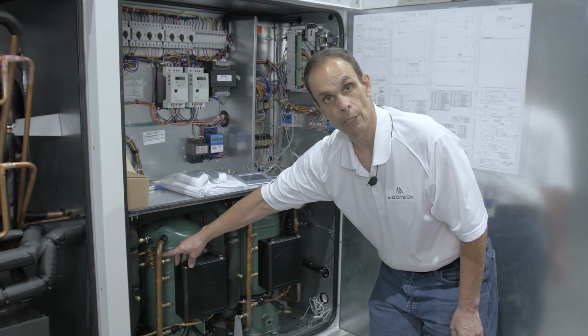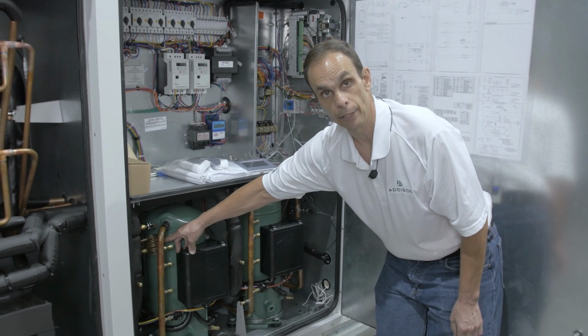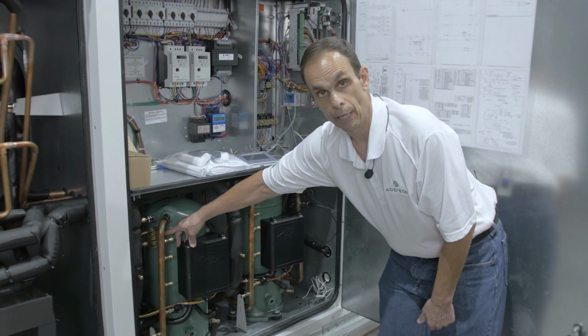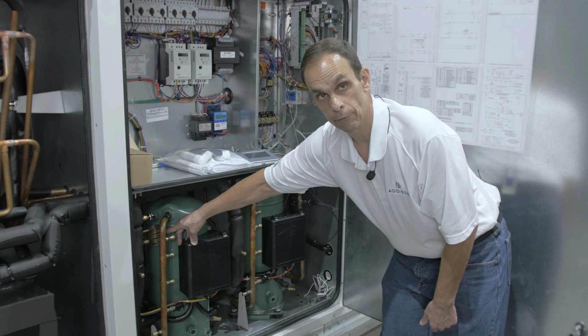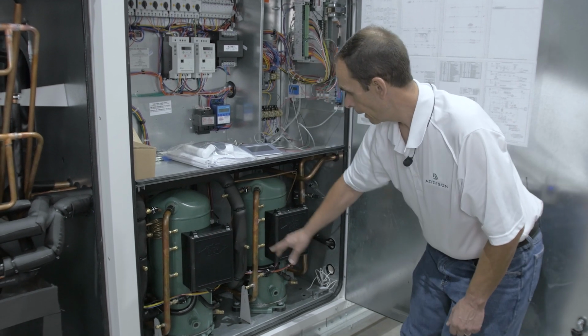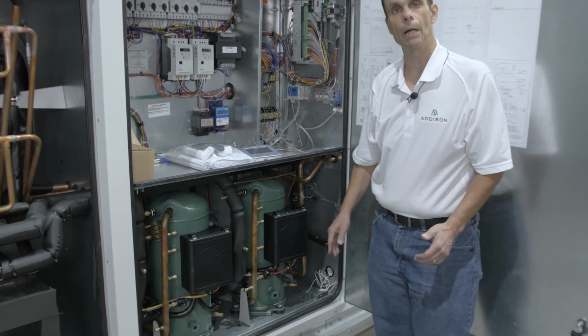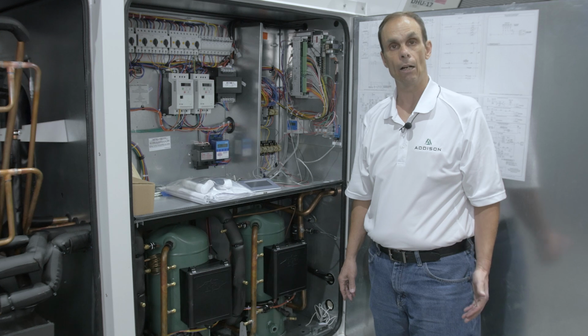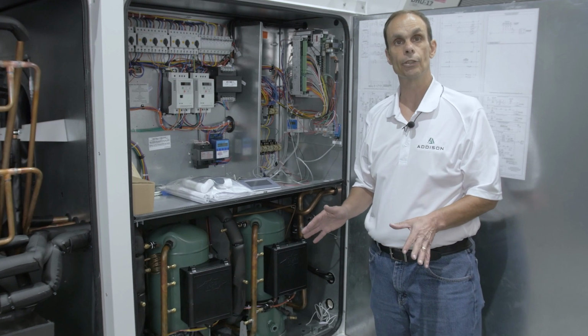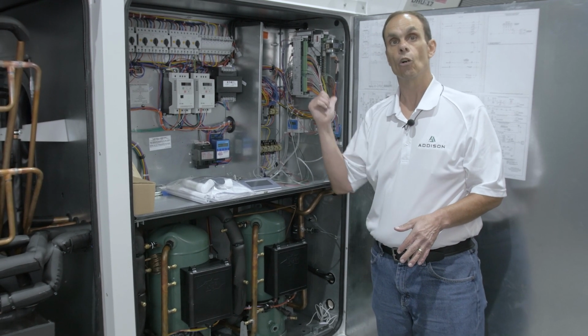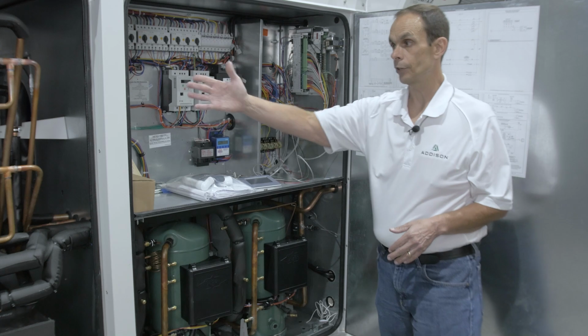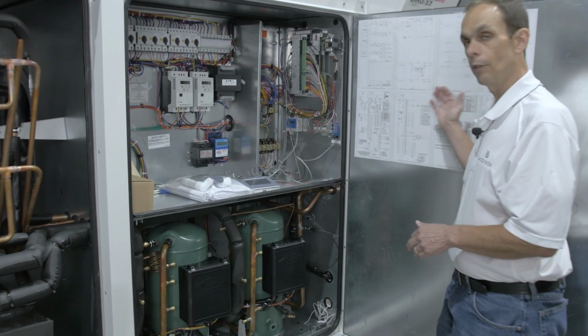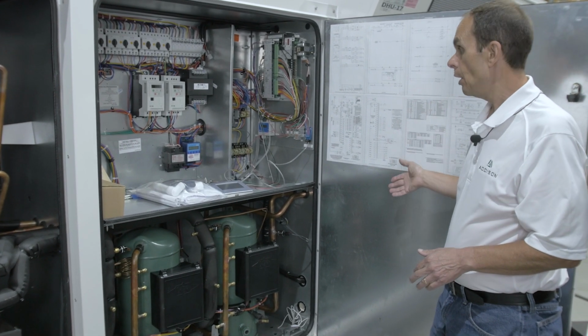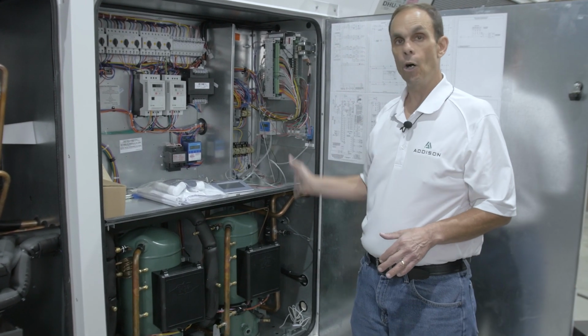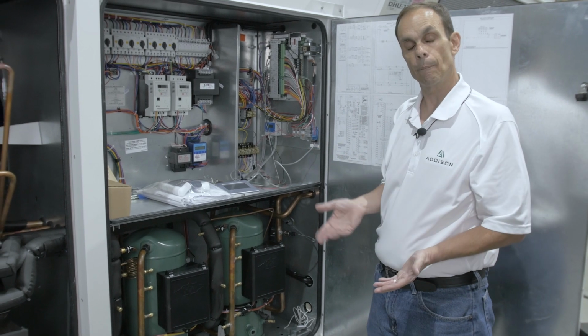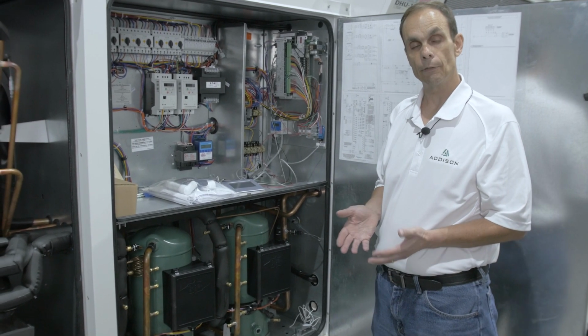Also in here is the bleed off cap tube and your bleed off solenoid, and that will help you identify when your reheat circuit is running and not running, or pulling the refrigerant out. In between both compressors, you have your modulating hot gas reheat valve, which will modulate and divert that refrigerant either to the condensers or to your reheat coil in the coil section over here. On the door, you'll have your wiring diagrams. So those are some of the key components, and where, if you never walked up to an Addison unit before.